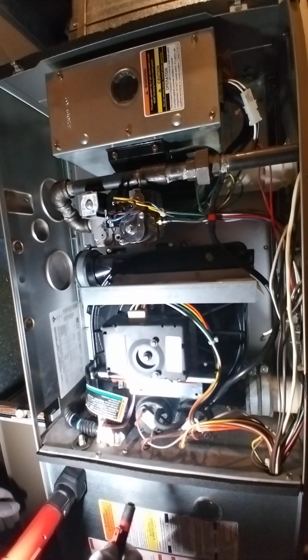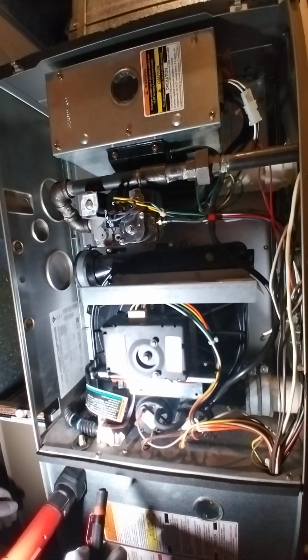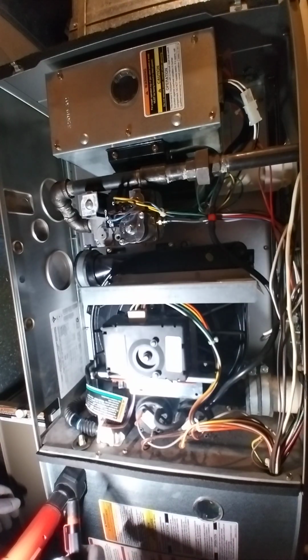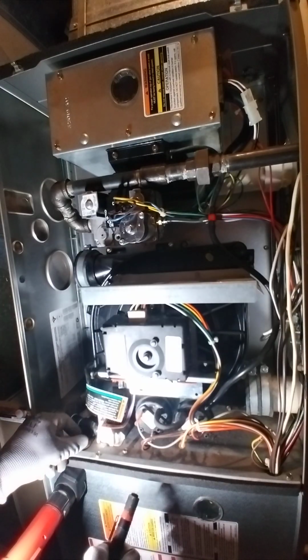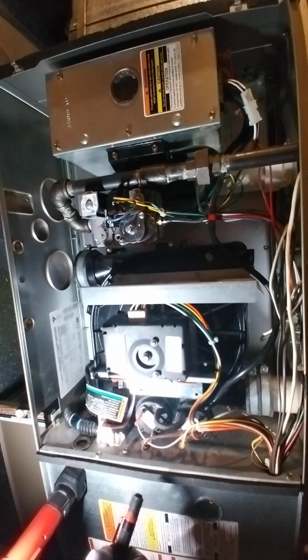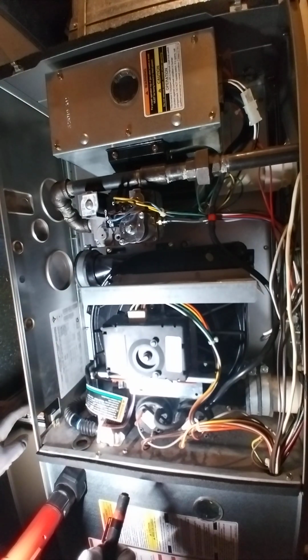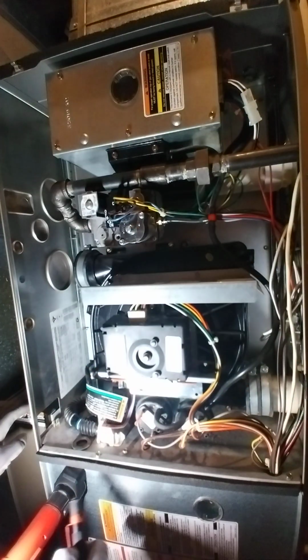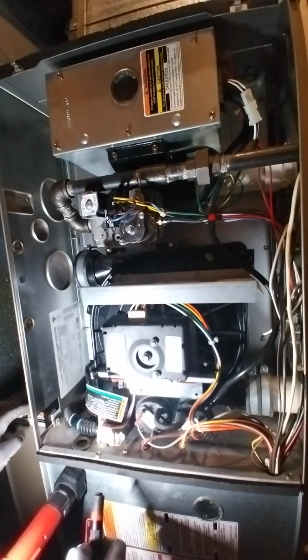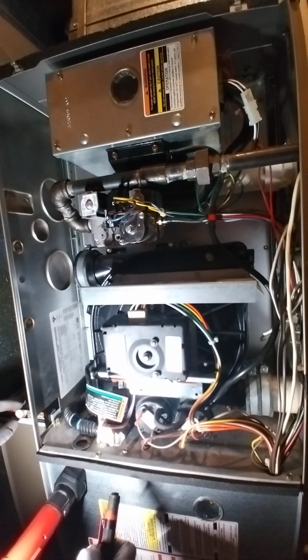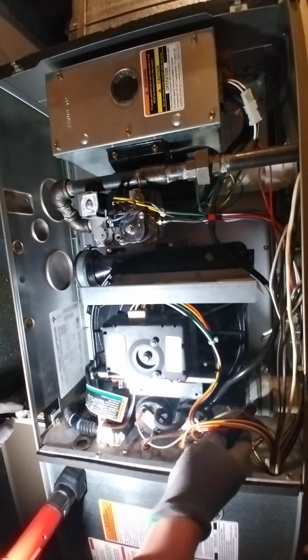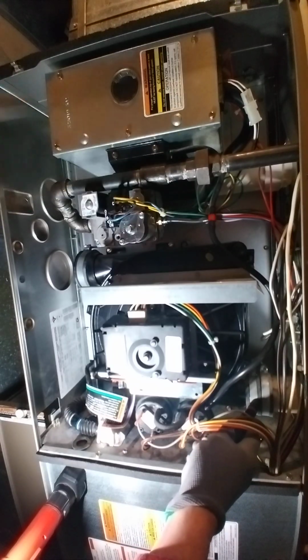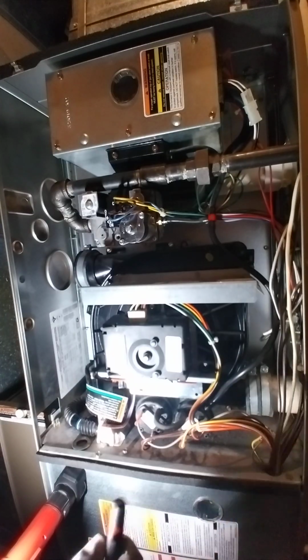So the particular error code that it was flashing at me was one saying that, yep, this low pressure sensor was in fact cutting out during normal operation, and that's what's leading to the shutdown. And again, this is only during the high heat mode, which is kind of confusing. So going through the manual, it listed a number of things, including blocked intake, a bad inducer motor not able to reach up to RPMs, and there's also a listing for the exhaust and the intake being plugged. It says if there's high winds, it can cause turbulent air that causes poor airflow inside the inducer.